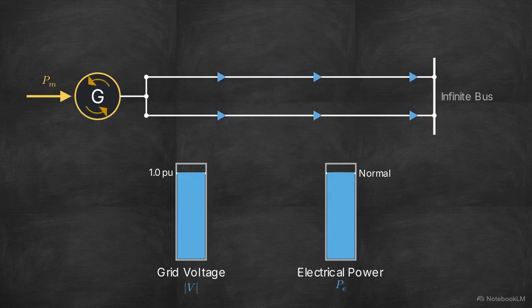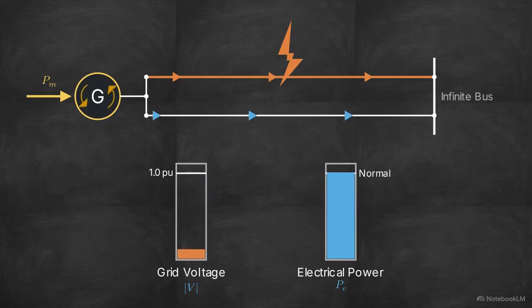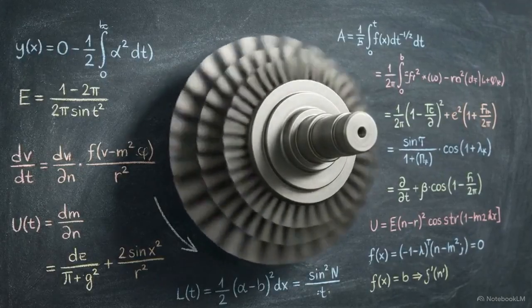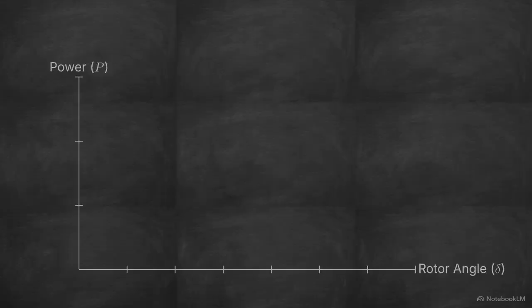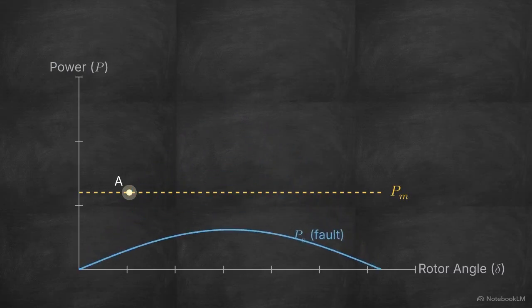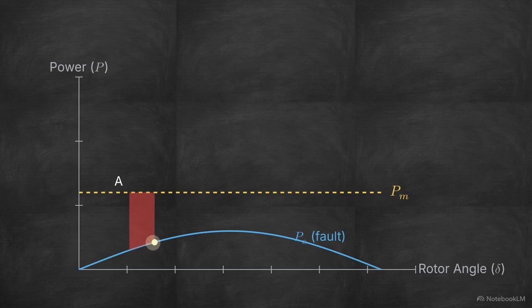We analyze this by upgrading our SMIB model to feature two parallel transmission lines. A fault strikes one branch. The short circuit causes the grid voltage to plummet. Electrical power output drops to nearly zero. While electrical output has vanished, the turbine continues forcing mechanical power into the shaft. This massive imbalance causes violent, unchecked rotor acceleration. On the power angle graph, the electrical sine wave collapses towards zero. The mechanical power line is now stranded far above the machine's electrical capability. As the rotor angle rapidly advances, it accumulates massive kinetic energy. This is the acceleration area, A1.